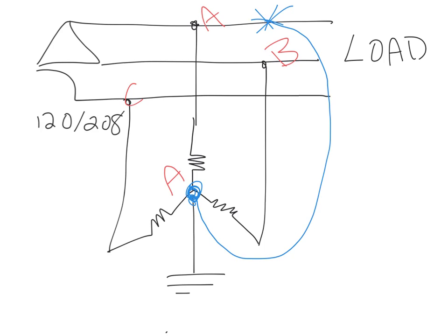So A and ground are now the same point. Well, we all know that we have three lines: A, B, and C. And up till now, across each one of the phases, this would be a phase, this would be a phase, and this would be a phase. And by the way, I'm showing little resistors—those are meant to be bulbs. Your ground detection device has three bulbs that are usually rated for line voltage, so in this case they would have to be rated for a minimum of 208 volts.